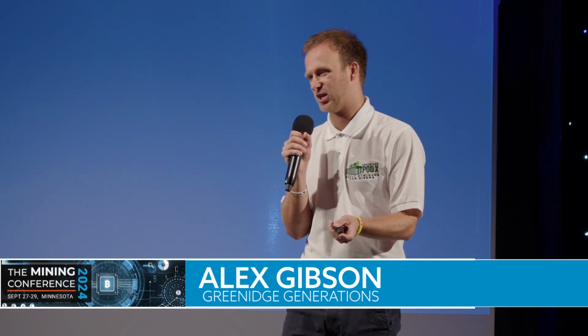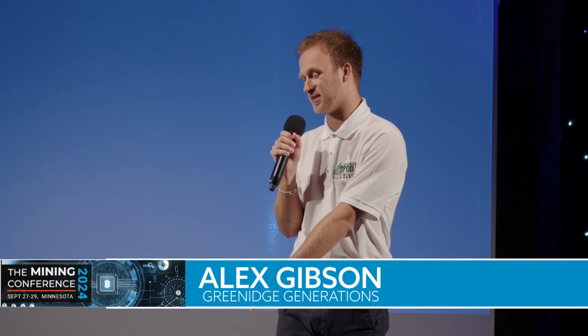So as I talked about, high negative pressure on your intake can also lead to high intake velocity, which is also an issue that you might feel and realize. Now, to understand high intake velocity, it's important to understand what the optimum velocity of your miner intake should be, which we found by doing a lot of airflow studies with the miners that we have. We did a lot of variation studies to try and find that optimum velocity and optimum pressure differential.